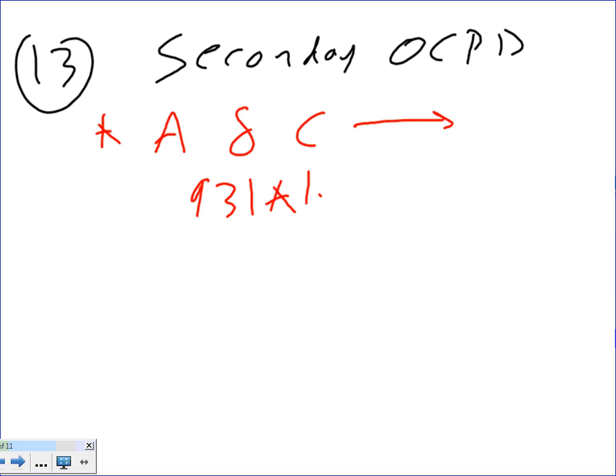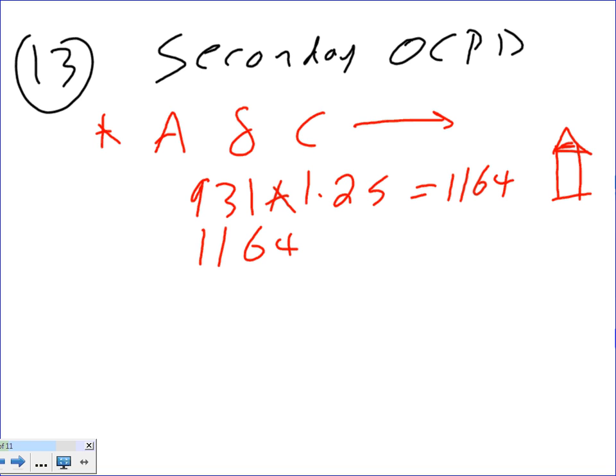times 1.25, equals 1164. If you look, there's a note that tells you to go up. So I'm going to take 1164 to 240.6, and have a fuse or a circuit breaker. What's the next standard? 1200 amp. A 1200 amp fuse or circuit breaker.